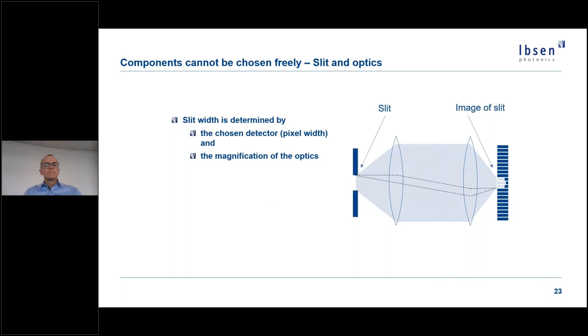If we change the magnification, it also influences the numerical aperture, which determines how much light the spectrometer can collect. So it's seldom a good idea to work with very large magnification, so normally it's going to be around 1. So that's a preferred magnification. So from this discussion, the slit width is also to some extent locked by the requirements for resolution.